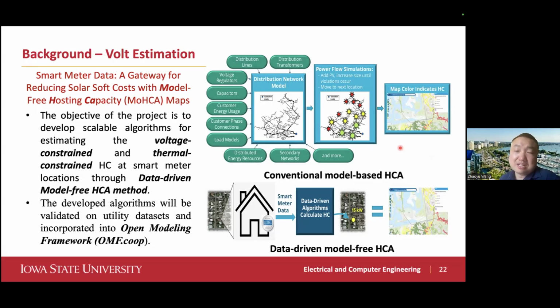If I have the system models, I model the system. I can run different scenarios of power injections from the solar and the load—the net load, solar load minus solar is net load. I can run different net load scenarios using power flow, and then I know the voltage. Then I can see if there's any voltage variation, how much that variation is, and how frequent it could be. That's a model-based method.